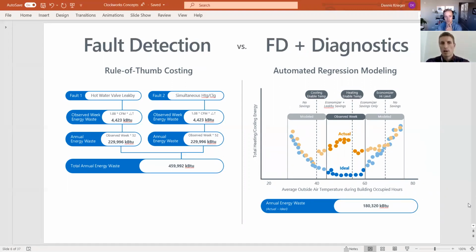This is also incredibly hard in a siloed rule approach where a fault lives in isolation. If I'm checking for leak-by on a hot water valve, but also checking for simultaneous heating and cooling, which one am I going to do my energy calc on? They're both essentially detecting the same issue.